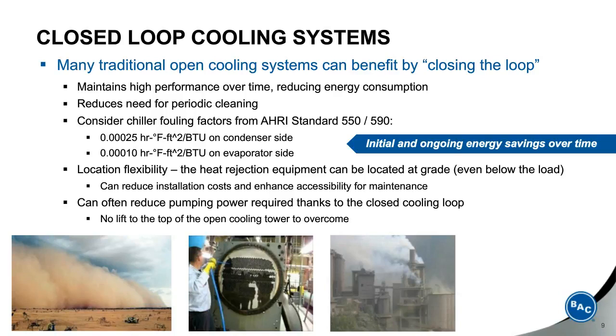Now, these are just the fouling factors as it comes from the factory in the rating. In the real world, the fouling can be much more severe, all the way up to 0.04 or greater, and that can have as much as a 44% increase in power required to do the same cooling duty. So keep that in mind.